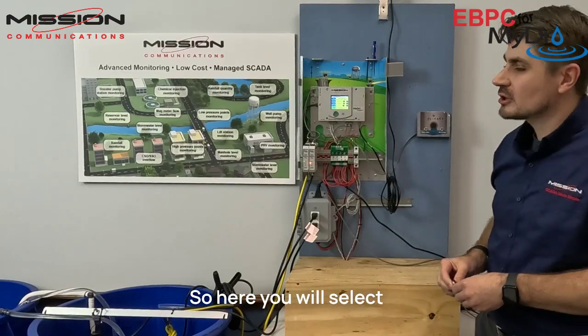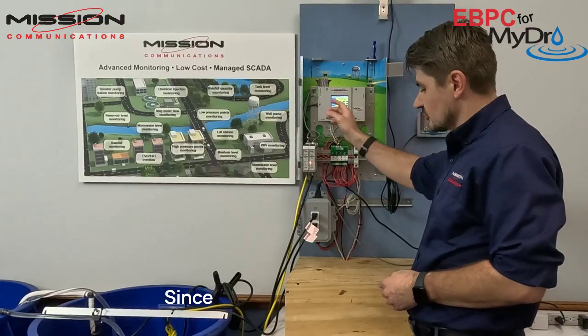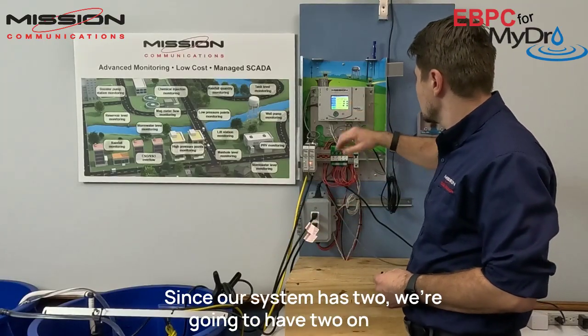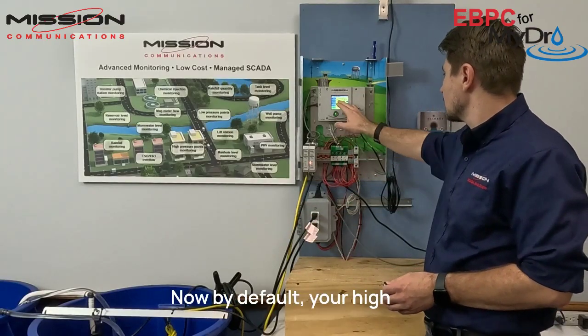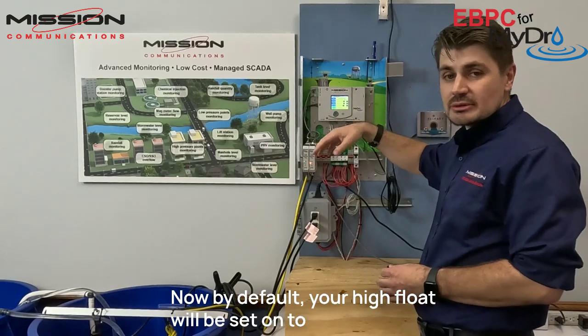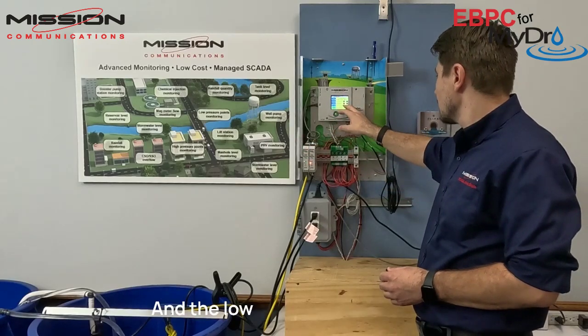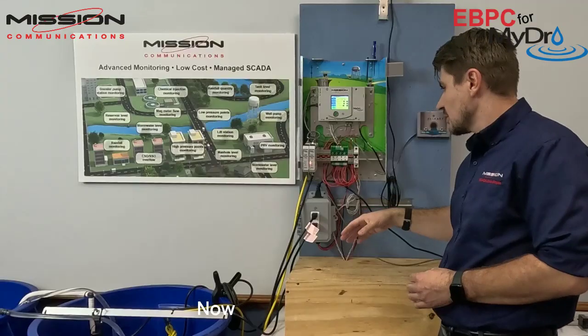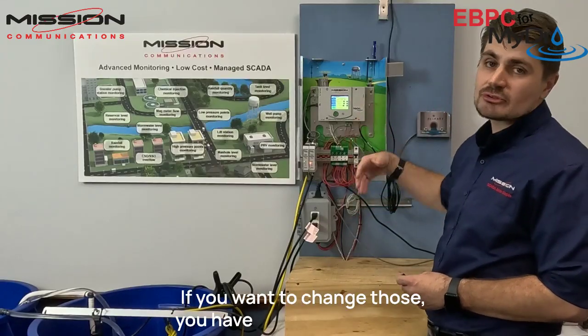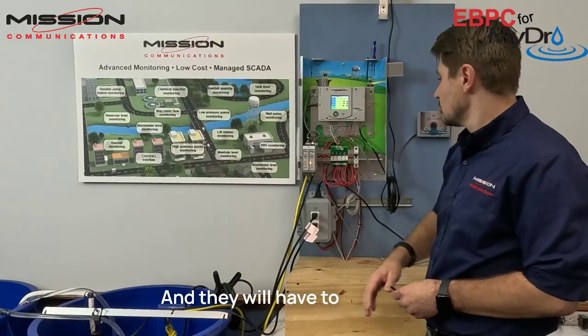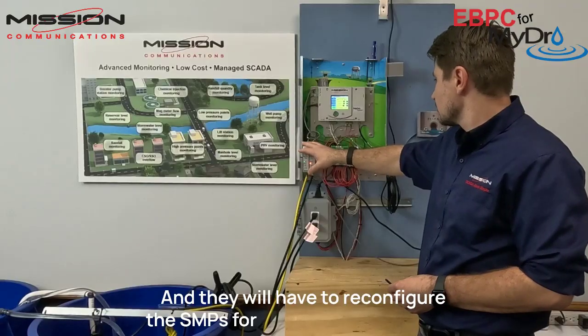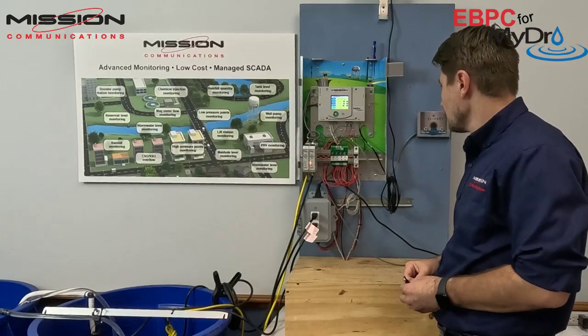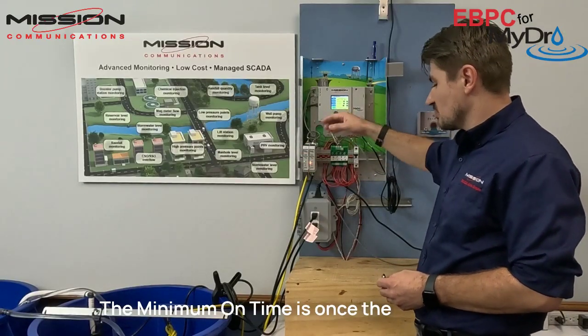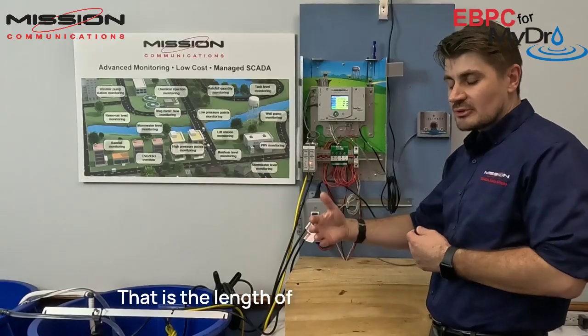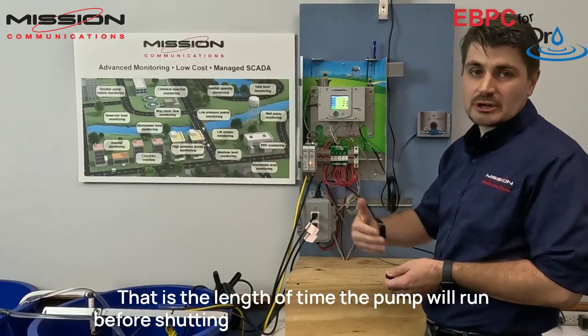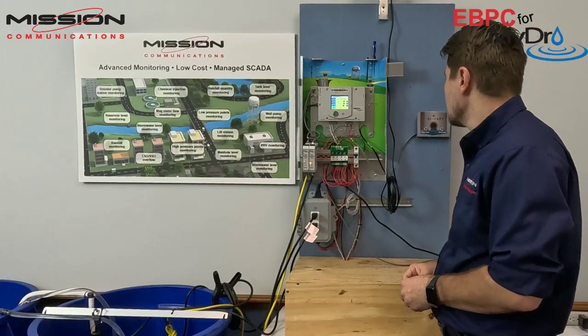So here you will select the number of pumps, 1 or 2. Since our system has 2, we're going to have 2 on here. Now by default, your high flow will be set onto digital input 4 and the low flow on digital input 8. Now these are standard. If you want to change those, you have to call tech support and they will have to reconfigure the SMPs for different digital inputs. The minimum on time is once a pump starts, that is the length of time the pump will run before shutting off in case it's a premature start.